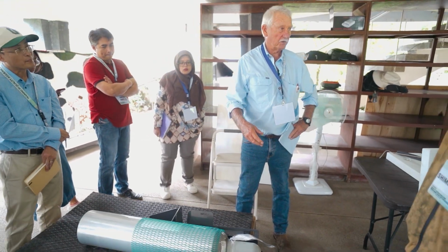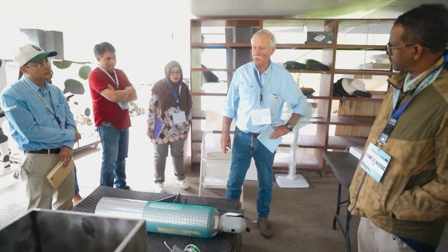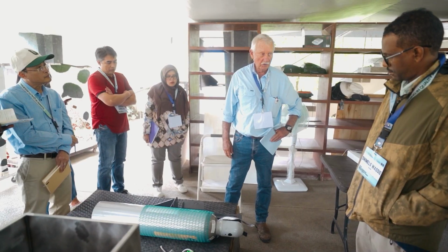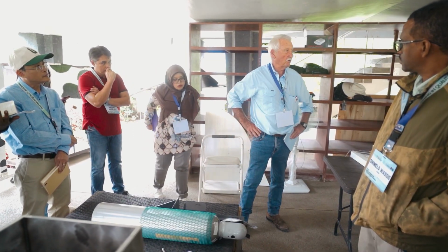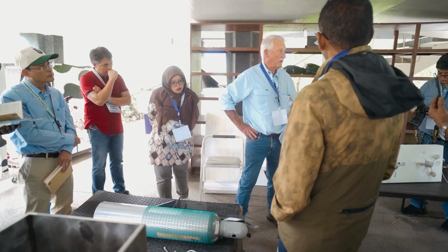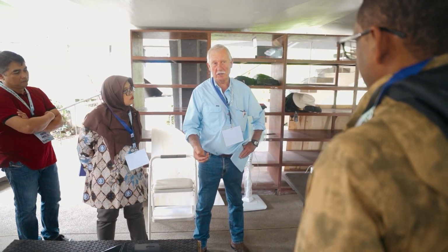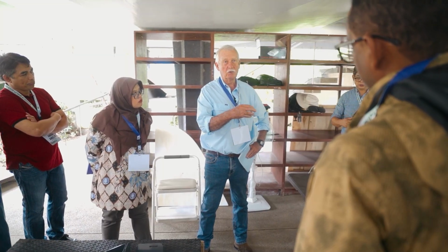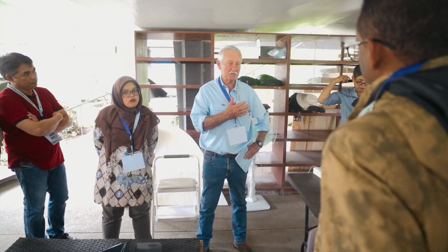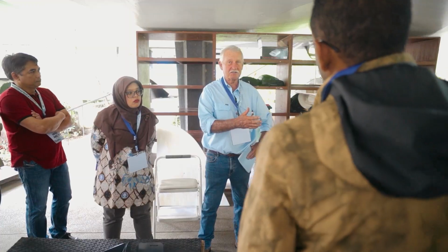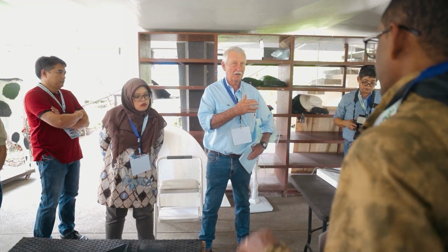This unit that is here is one of the newer units. The older units, and I don't know who has them, would have the auto calibration. The older system came with two calibration gases, which was our normal way of doing calibrations: a zero gas, which was nitrogen, and a span gas of known concentrations.